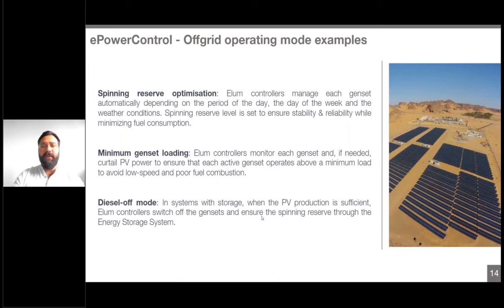These are some examples of the features that we will be providing for such systems. As I said, there is the minimum genset loading for most of our projects, but we can also provide the spinning reserve optimization or management, depending on the genset or the BSS. And we can also provide the diesel off mode. In case the size of the batteries can overcome the load available on site and the SOC of the batteries is high, we can turn the gensets on and off in order to reduce the fuel consumption.